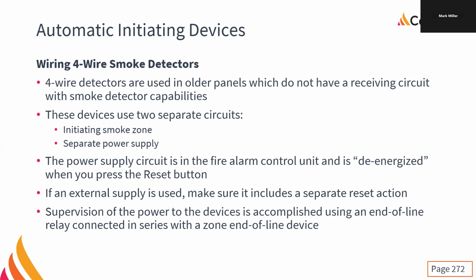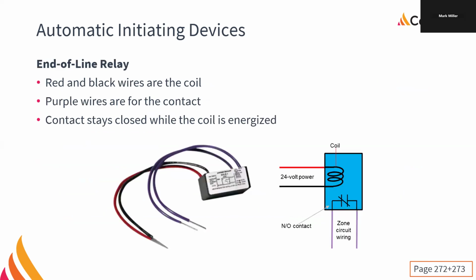If we do not provide that 24-volt power to the smoke detector, it is obviously not going to work. So we need to make sure that we have the 24 volts, and we're going to accomplish that by using an end-of-line relay. The end-of-line relay is just a coil that gets powered by the 24 volt. This is after the last of the devices, and it energizes a contact, right? It's a normally open contact, so it closes when it's energized. And we put that contact in series with the end-of-line device on the zone. So if we lose the 24 volt, we get the open circuit trouble.